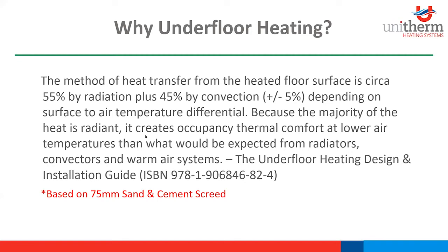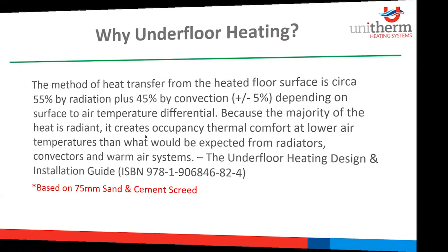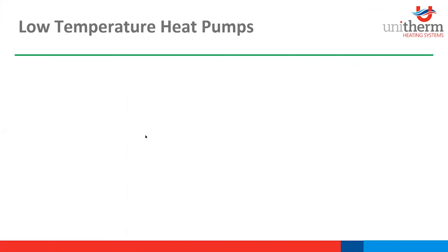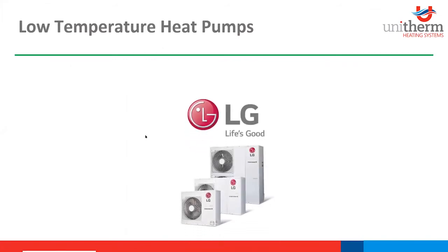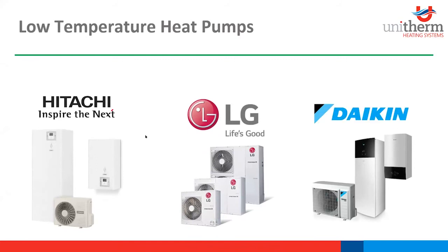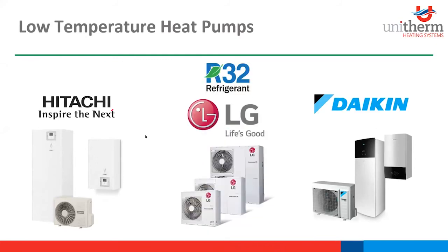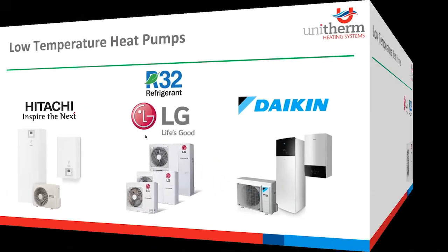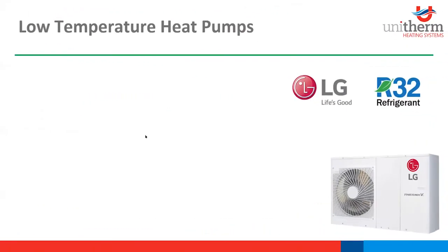So we're basically just saying, that's based on standard 75 mil cement screed, majority of your heat is coming by radiation, and this gives you more thermal comfort. So if we increase the thermal mass, we're increasing the amount of radiation and therefore increasing the thermal comfort, and we'll get away with lower temperatures. So a bit on low temperature heat pumps here: LG, Daikin, Hitachi, all our heat pumps in the Uni-Therm here, basically they're all R32 refrigerant. So we're going to talk to you a bit now on the LG Therma V R32 monoblock. It's the world's first R32 monoblock.